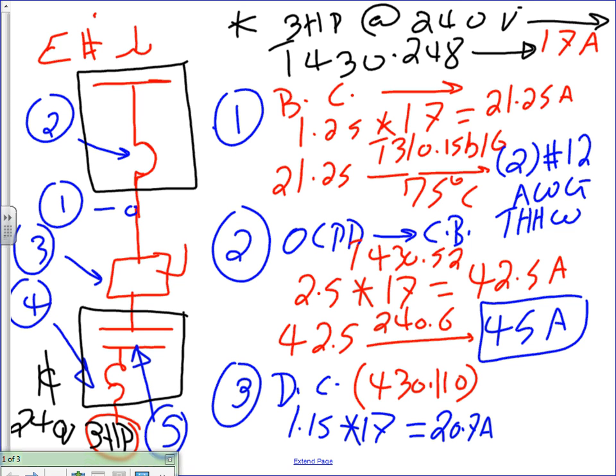If you don't believe, Chad, please go to 430.110. It tells you you have a disconnect. It's 1.15. Yes, sir. Correction, 19.55. That's why I need seconds, guys. How much? 19? Yeah, 19.55. Okay, amps. 19.55. Okay. All right, so that's your disconnect.